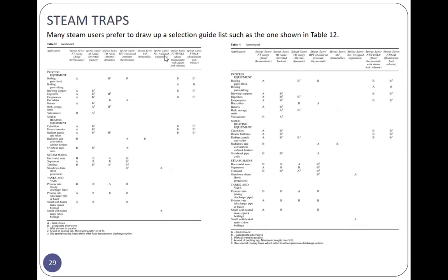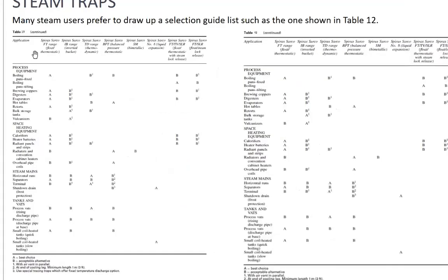Many steam users prepare selection guide lists such as the one in table 12. For example, table 12, this is table 19 here. Sorry, there is a mistake: table 19, not table 12. Here is the type: float and thermostatic. It can be used for boiling, brewing, coppers, evaporators. The inverted bucket is an acceptable alternative. The A is the best choice. Those with no entry are not applicable and not recommended.